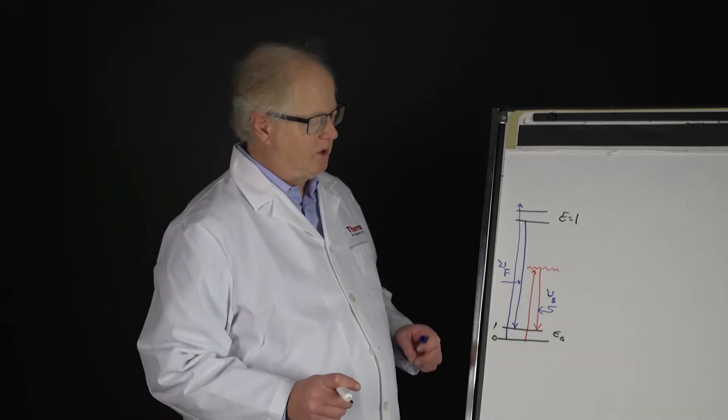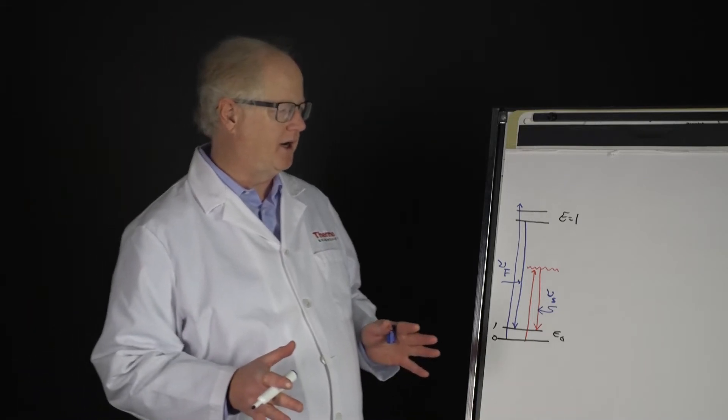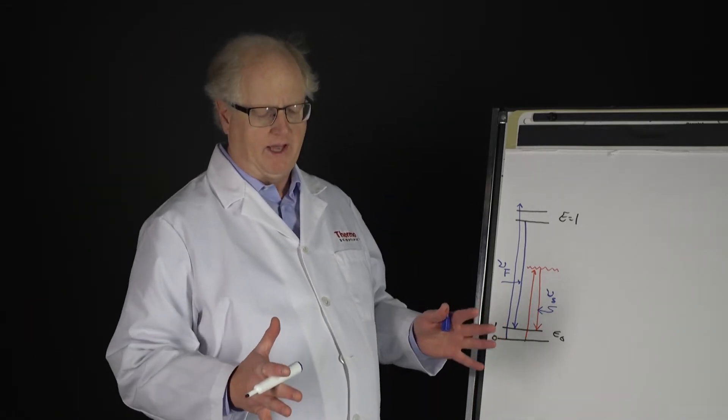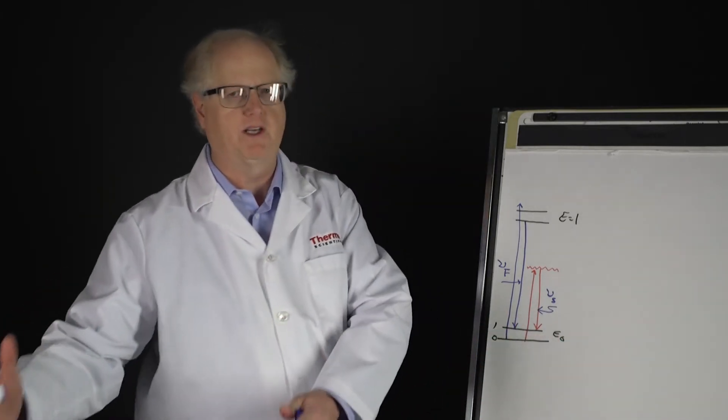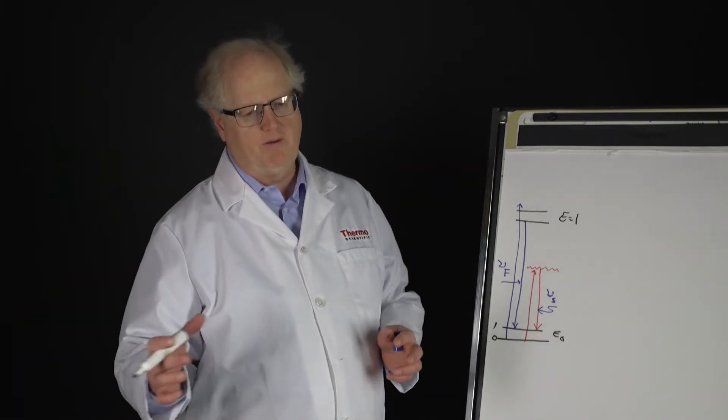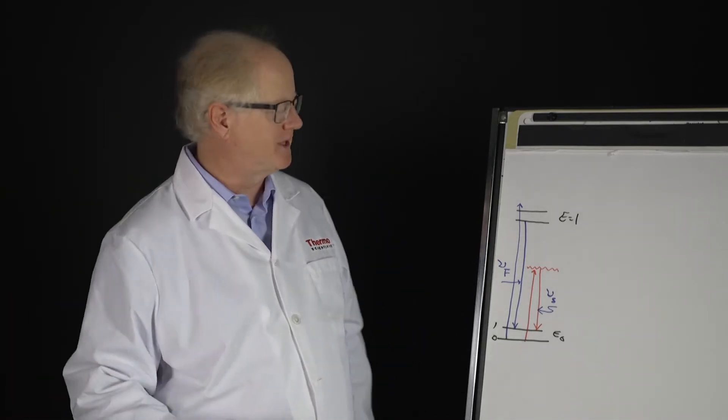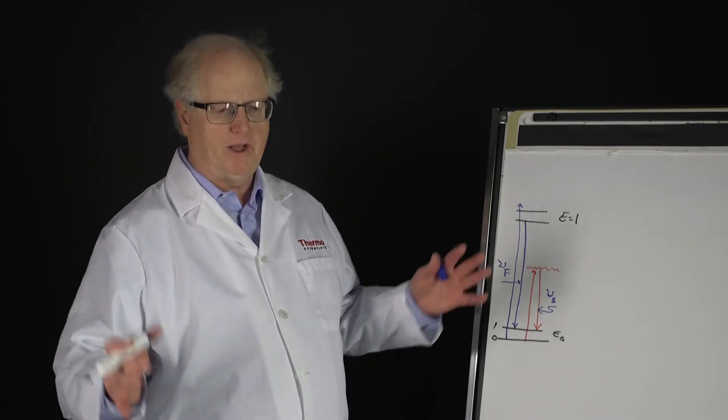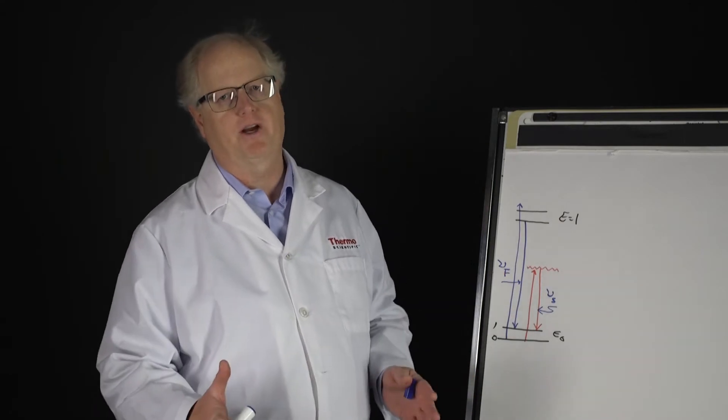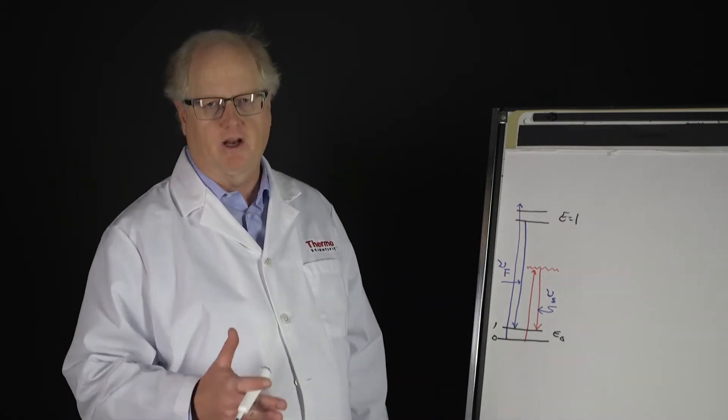On the Thermo Scientific Nicolet iS50 FTIR spectrometer, we have a Raman module that fits right into the sample compartment. It doesn't require sitting on the side - the older previous generation instruments had a large module that sat on the side, but this module just fits right in the sample compartment and it utilizes the interferometer and detector scheme of the Nicolet iS50 spectrometer.